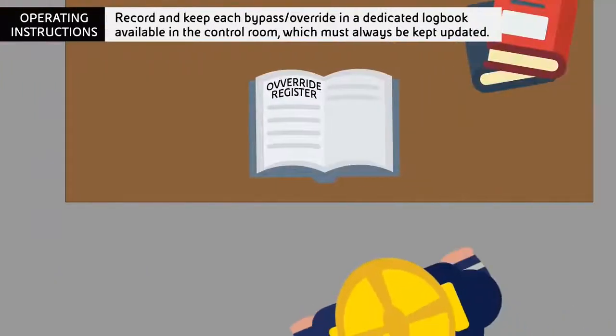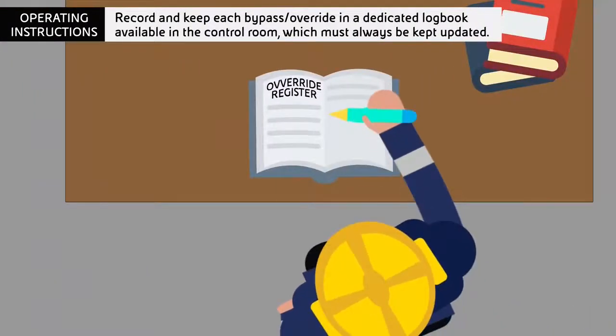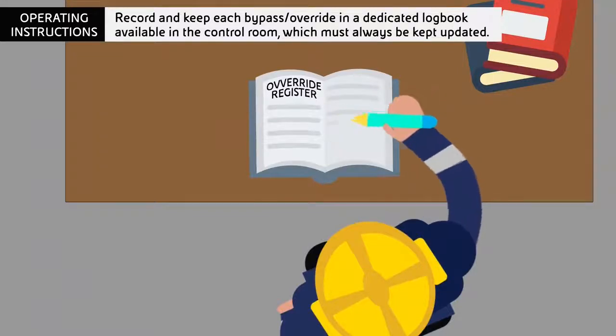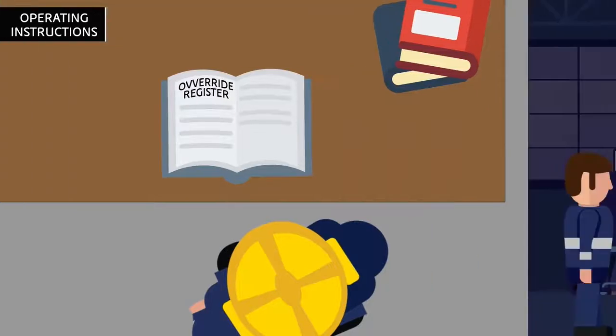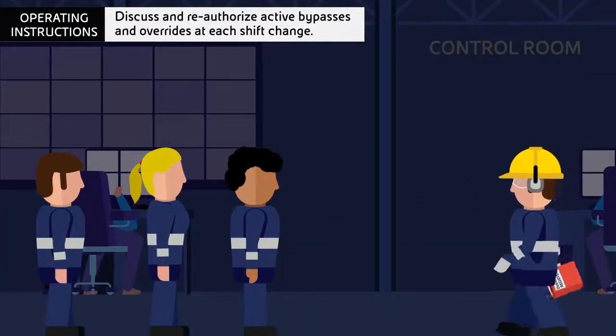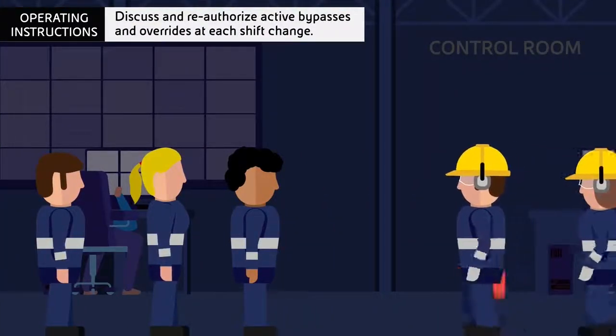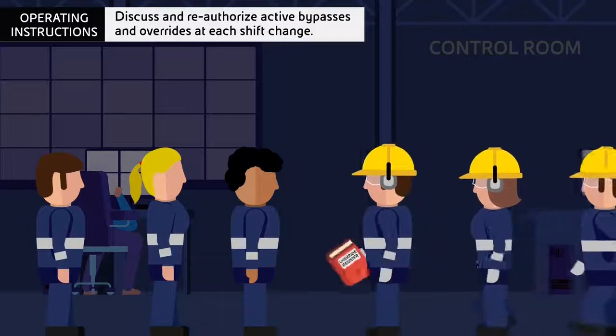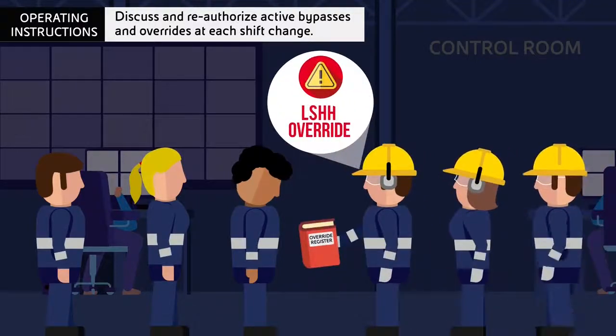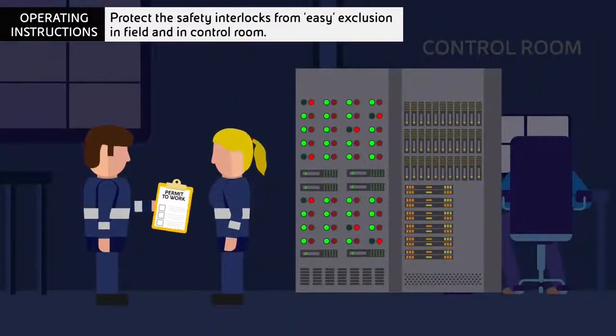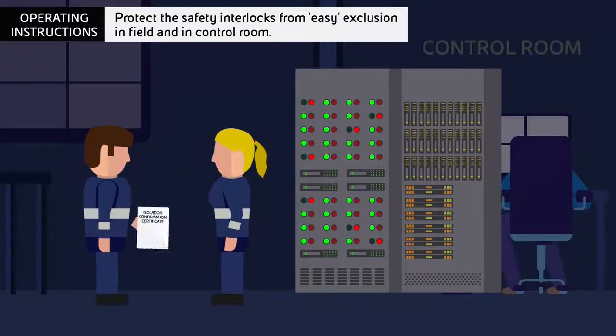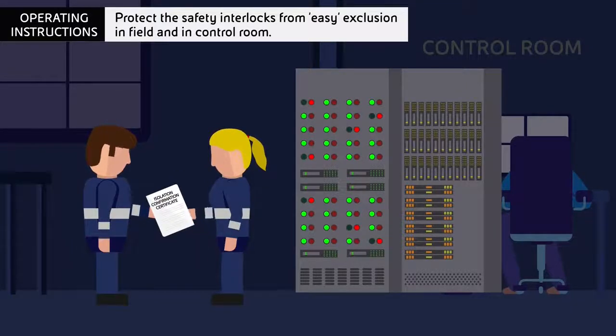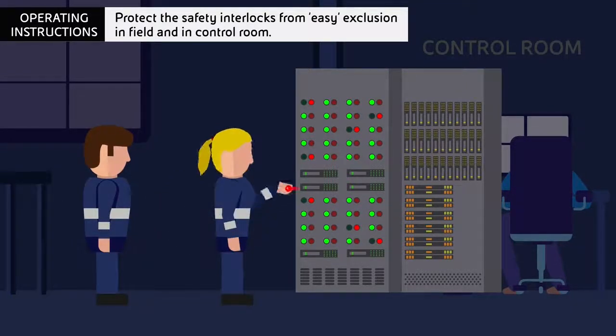Record and keep each bypass override in a dedicated logbook available in the control room, which must always be kept updated. Discuss and reauthorize active bypasses and overrides at each shift change. Protect the safety interlocks from easy exclusion in field and in control room.